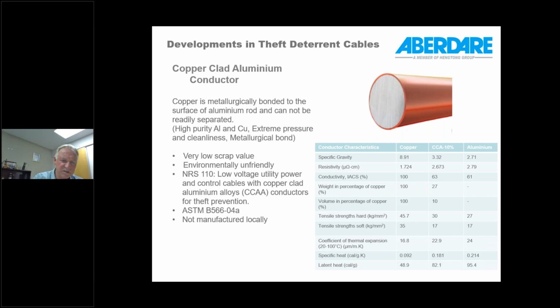The NRS standard was developed, 110, which is the low voltage utility power and control cables with copper-clad aluminium conductors for theft prevention. So this was published, I would say about 3 years ago, and it also hasn't seen the uptake that it was thought it was going to have. The main interested parties were City Power and also Eskom, and although Eskom had put out a request for information, none of the local manufacturers actually offered cable containing these copper-clad aluminium conductors for the reasons that I mentioned.